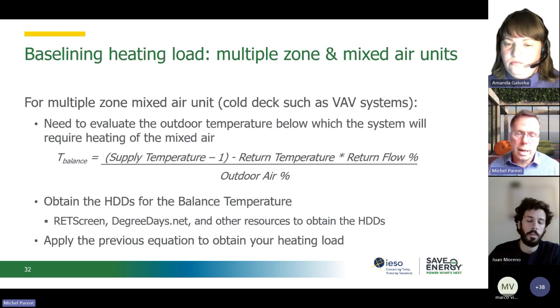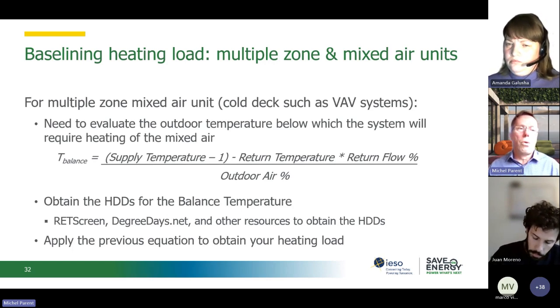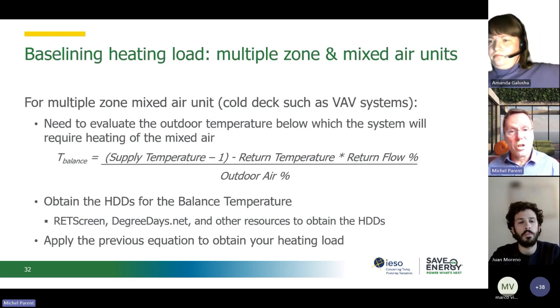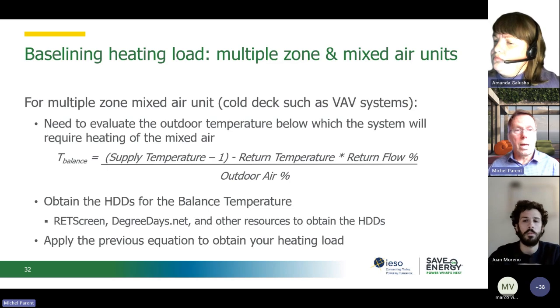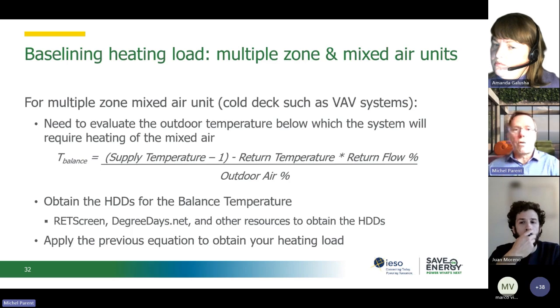Now, where are you going to get those heating degree days? There are some really easy resources. You can use RETScreen. It will provide you heating degree days at different balance point temperatures. And there's a website called degreedays.net where you can enter the schedule that you want, your balance point, and the location anywhere in the world, and it will give you those heating degree days. So even though there's some pretty easy math involved, you can get the estimate for heating for your cold deck mixed air system.